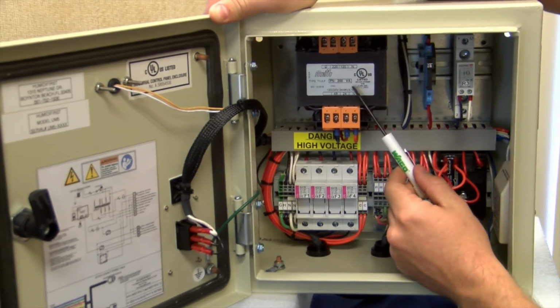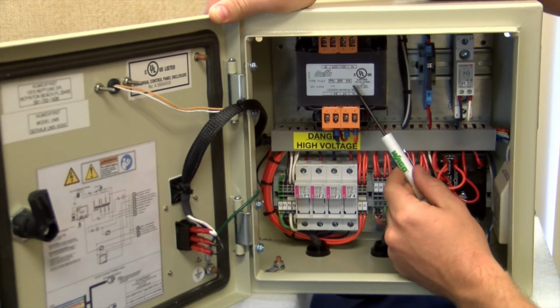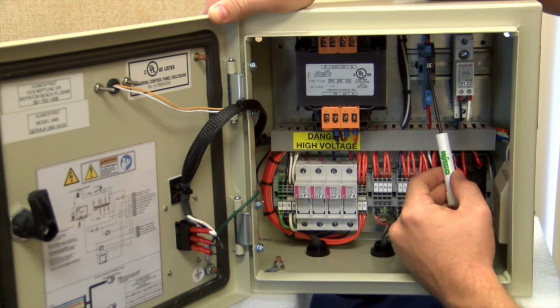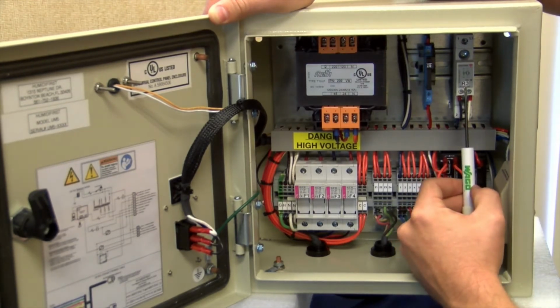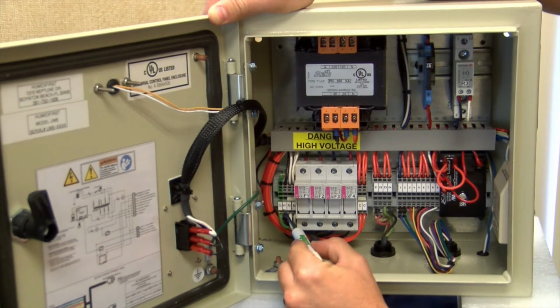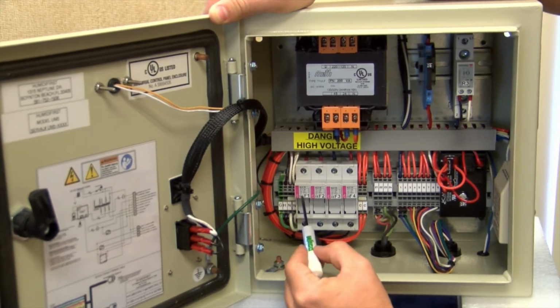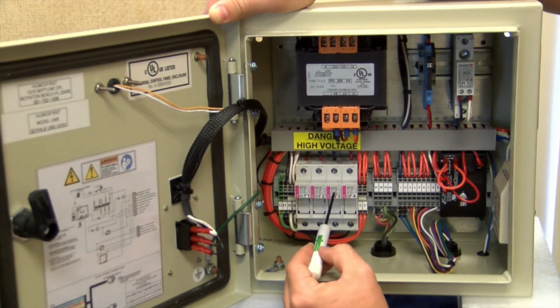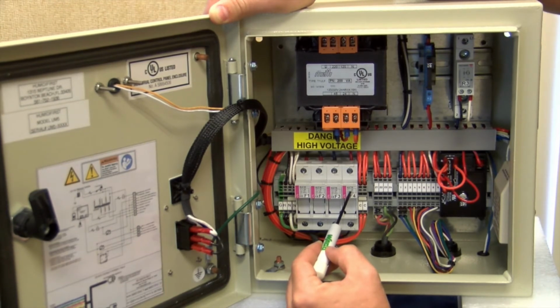Here is your transformer that transforms your incoming 120 power. Here is your R1 relay, which controls your low water safety. Here is your R3, which controls your transducer's operation. Here is your incoming 120 volt power. Here is your F1, which is the fuse for your incoming power. F2 is your fuse for your internal 120. F3 is your 48 volt fuse for your transducer circuit. F4 is your 24 volt fuse for the solenoid and float switch.